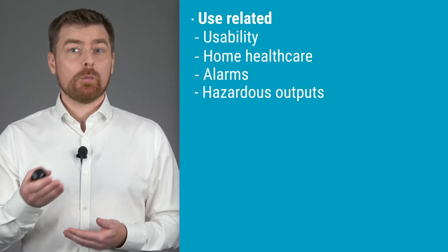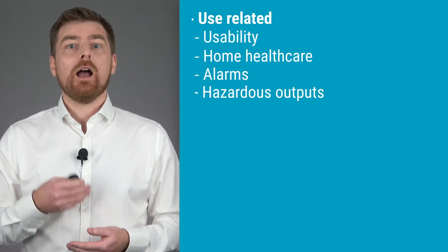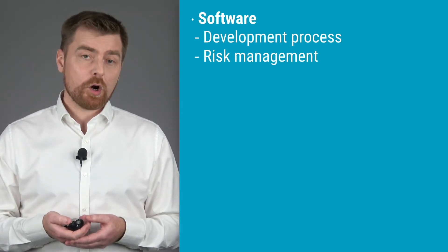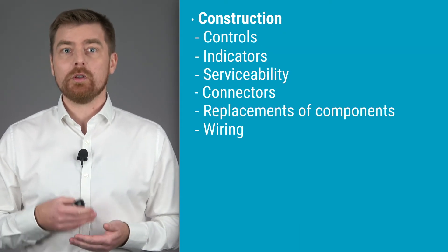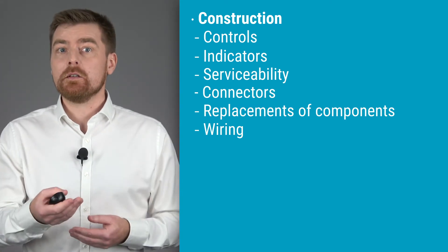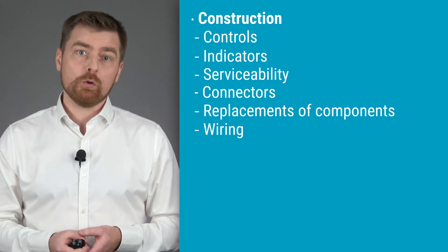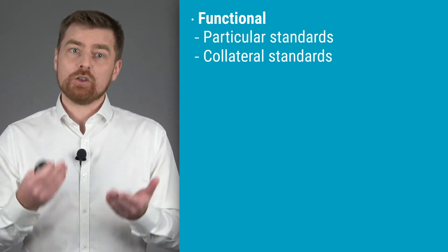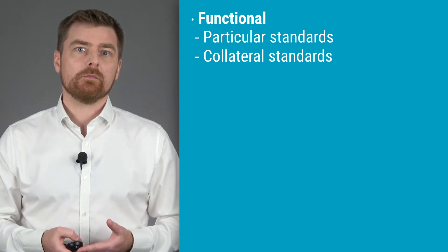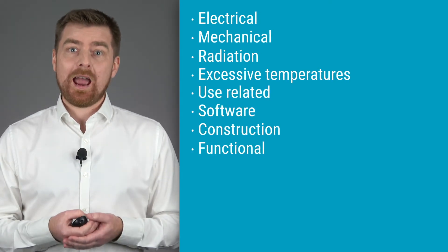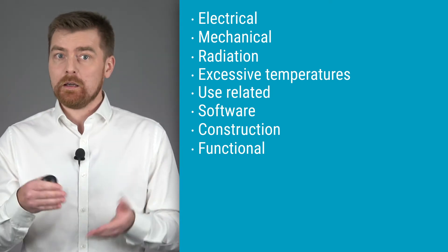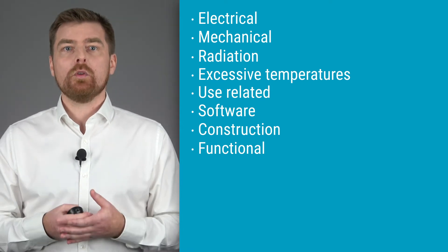Use-related requirements include usability, home healthcare, alarms and hazardous outputs. Software requirements include requirements for the development process and risk management. Constructural requirements relate to controls, indicators, serviceability, connectors, replacement of components and wiring. Functional requirements are often defined in particular standards and in some of the collateral standards. All these requirements and other hazards relevant to your device need to be identified and managed through the risk management process.